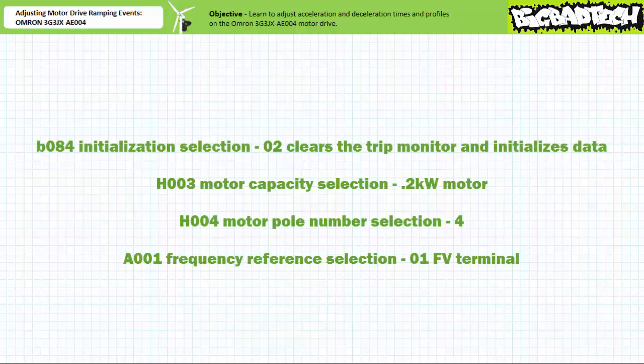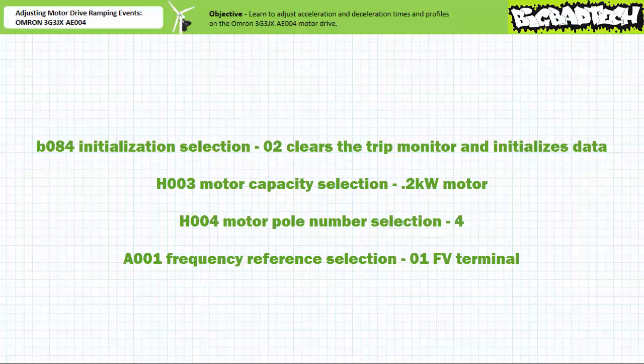We'll initialize the drive to a default state and clear any errors using the initialization and protection parameter B084. Then we'll program it to recognize a 200 watt motor with a nominal rotational speed of 1800 RPM using the motor settings parameters H003 and H004. Finally, we'll program the drive to recognize an external speed potentiometer input using extended function parameter A001.